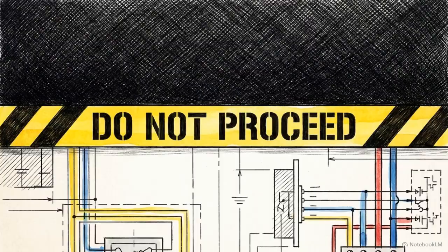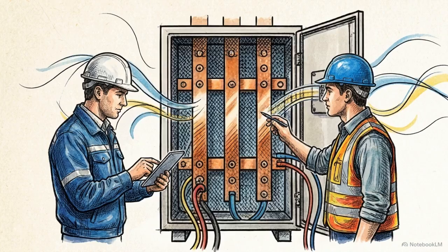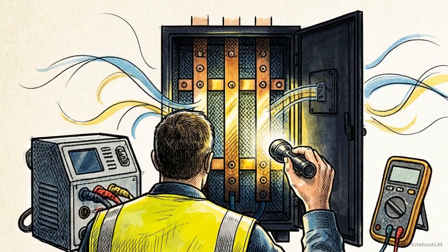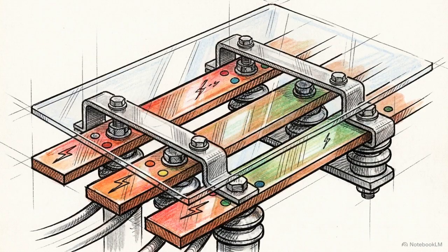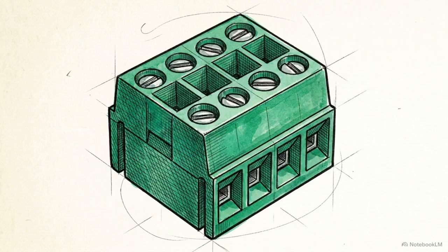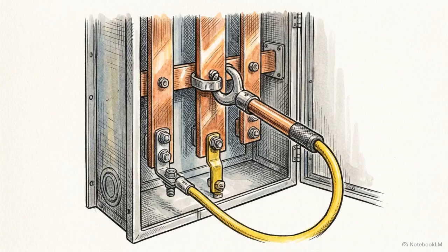The culmination of the testing protocol is the hold point. This is a procedural barrier, mandating that no single technician has the authority to release the panel for active service without witness verification. An independent operations witness executes a mandatory physical walkdown. They verify physical barriers are restored, temporary test links are removed, and every bus bar is completely discharged.